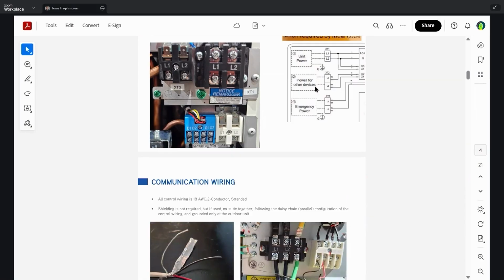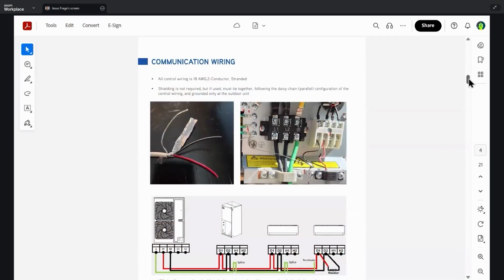It's not needed in every application, but the main time you would use it is in commercial. We have supplied a wiring diagram here out of the service manual that explains exactly where those terminal blocks are sitting in the unit. And here's a reference photo of a GMV6 R32 3-ton unit. So for the communication wire, nothing really changes on this side. We're still going to run our 18/2 from the outdoor unit. It's going to be D1 and D2 and the ground.